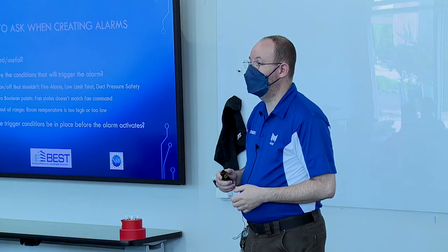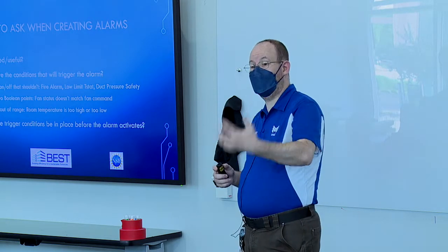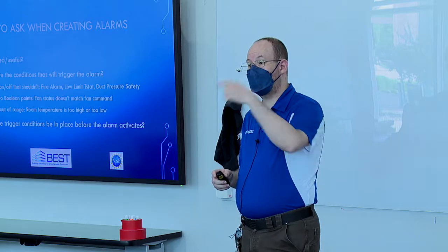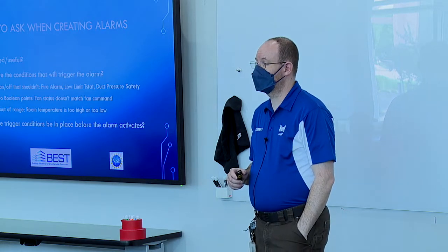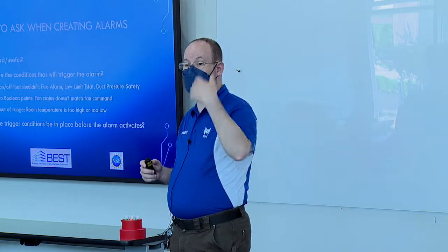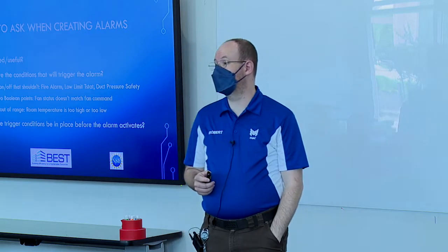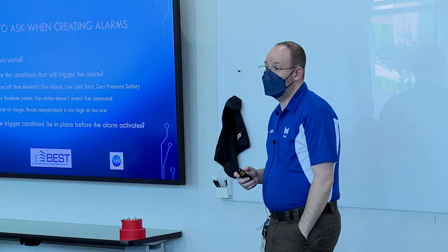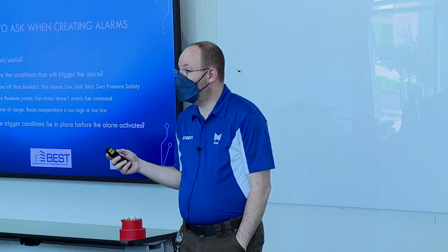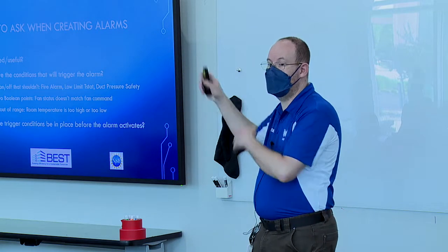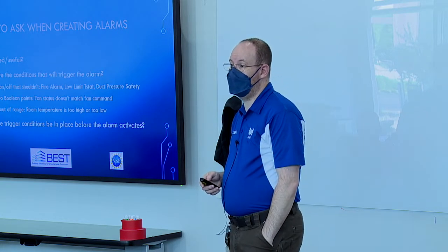Or, on the converse side, something that we don't always think about, but we need to, especially from an energy standpoint: I told the pump to turn off. Status says the pump is still on. Somebody put it in hand. Somebody turned it on to manual mode because they needed it to run for a maintenance purpose or something, and forgot to turn it back to auto. Happens. Also, that could be a sign that we have a bad status signal. Somewhere we've got a shorted wire, bad status donut, list of possibilities. But it's something that should be investigated.